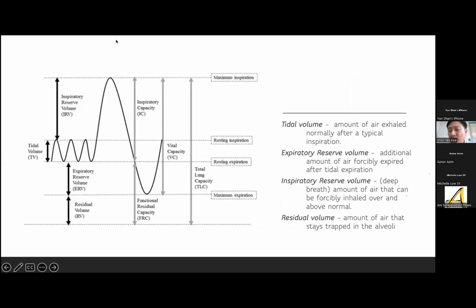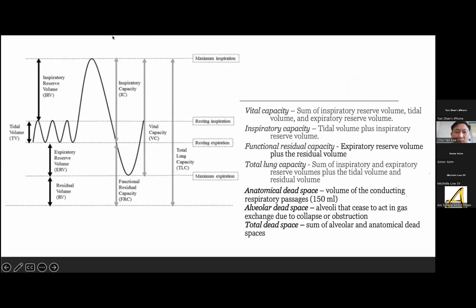If you use volume control ventilation, you must always make sure the tubing compliance is being compensated. If the compensation is not on, the calculation will not be accurate, so you'll be misled by the numbers, because your minute volume and tidal volume will be calculated as such.